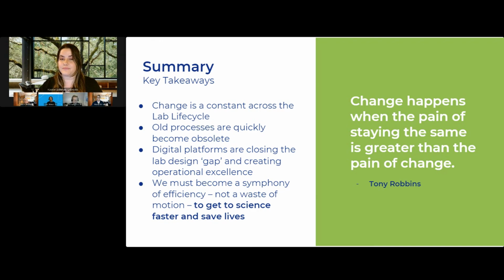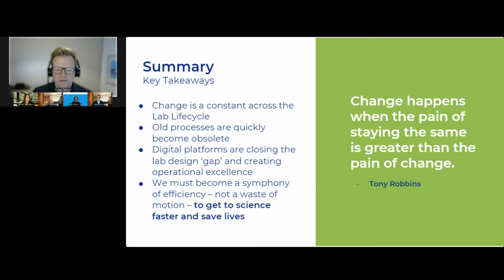Well, certainly, the way that we collect the utilization data, we can do that in a variety of different ways: either monitoring the electrical signature, so the current signature of an instrument, knowing when it's running and when it's idle, or getting it from data files without affecting data integrity, or from the instrument itself. All that data comes together, and then we collect that in a data warehouse, and it goes to our dashboards, but we can send that somewhere else.